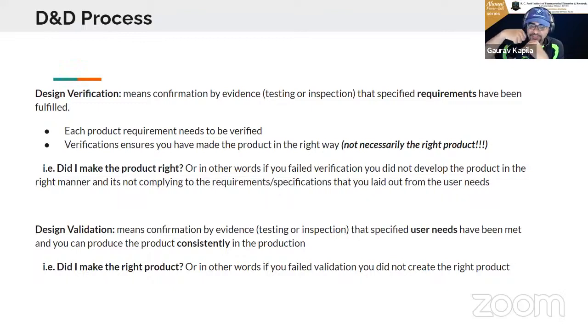And did I use the same force? That is my design input. So if I used 5 newtons of force for 20 minutes, that was my design input. And I demonstrated by the testing, then it means that I verified that requirement. In the same way, we have sub-requirements that need to be verified, and I can say that I'm making the product in the right way. Like when you cook food, you keep checking, you keep adding salt, and you keep tasting until the salt reaches your user needs, which is swad anusar, as we call it. So that is the design verification you are doing throughout this process.